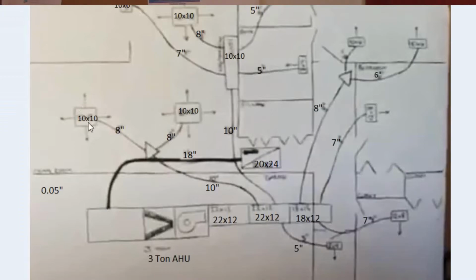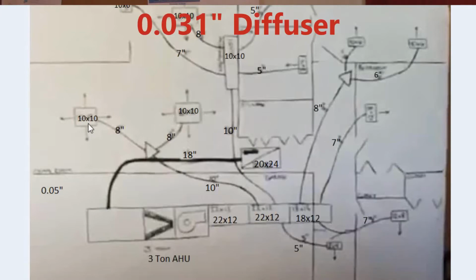So let's just say we are using an actual 10x10. I'm going to go off of what this guy has, a 10x10 ceiling diffuser. We take that ceiling diffuser, we look it up in the book, and we find that a 4-way ceiling diffuser, 10x10, has a pressure drop of 0.031.